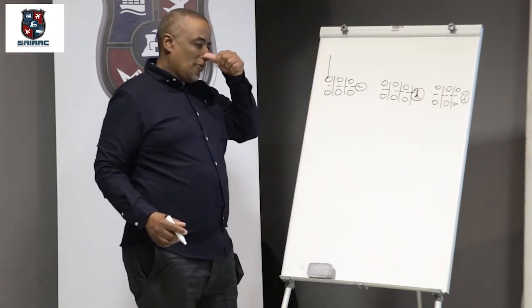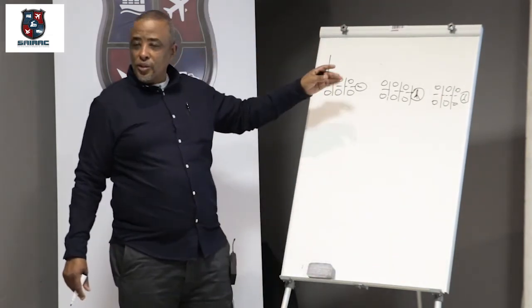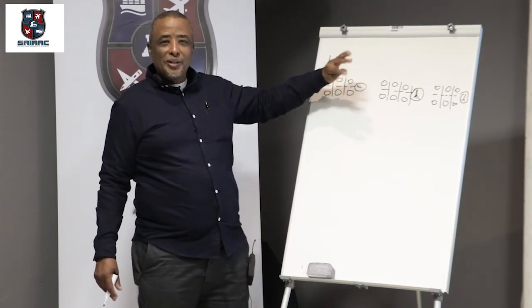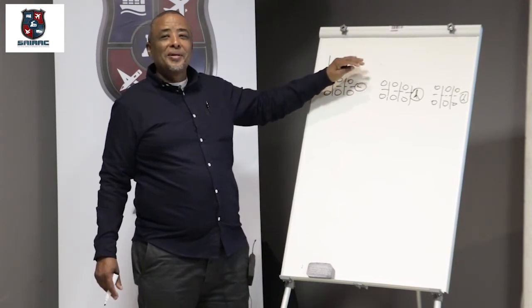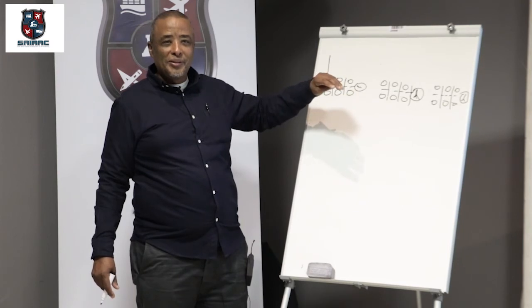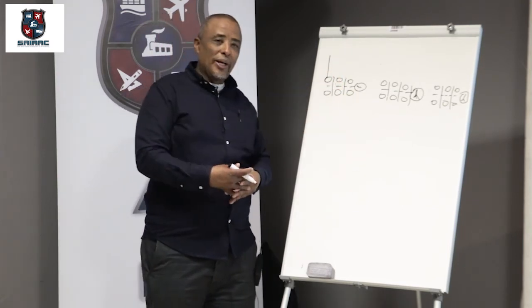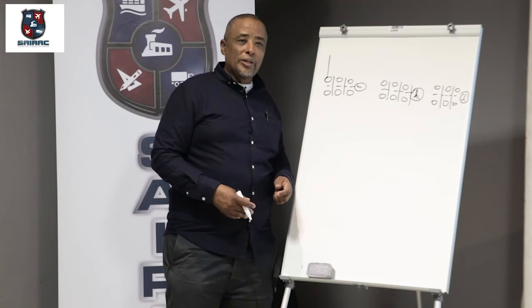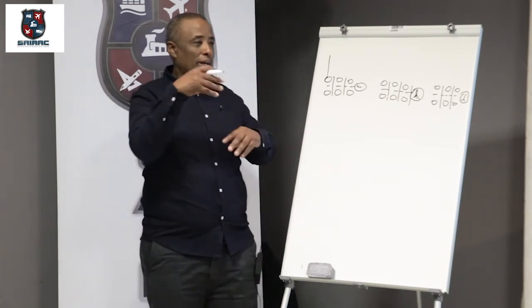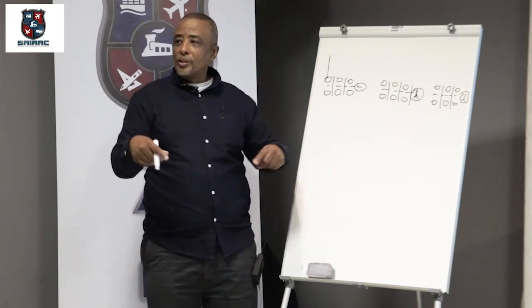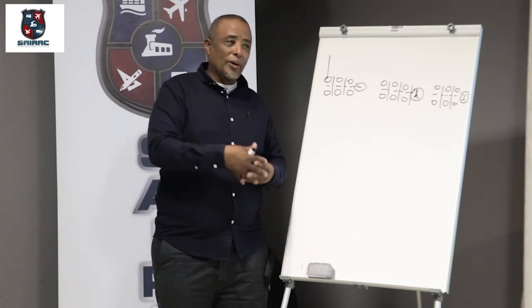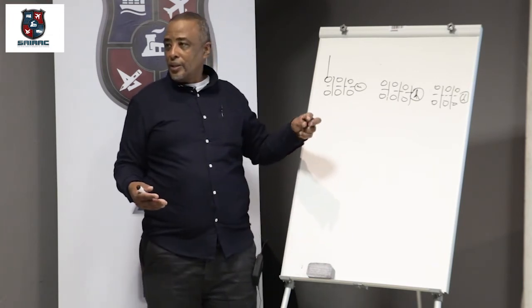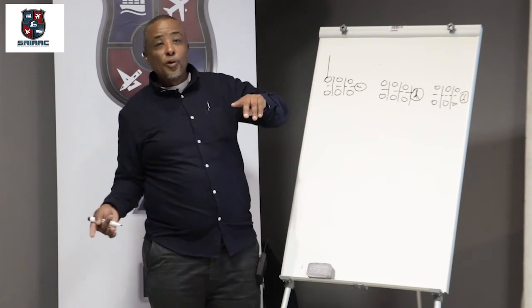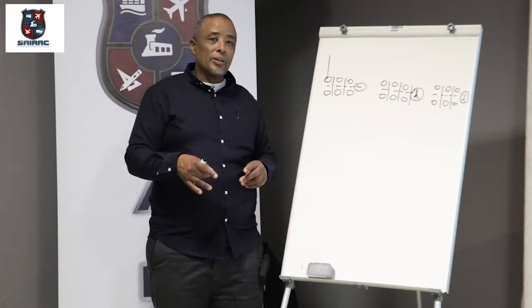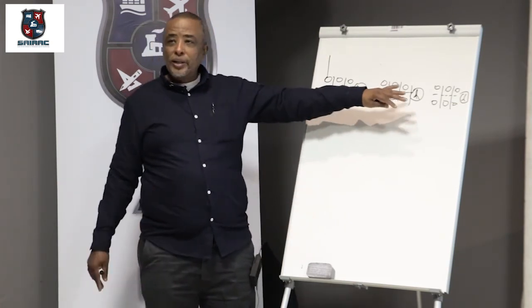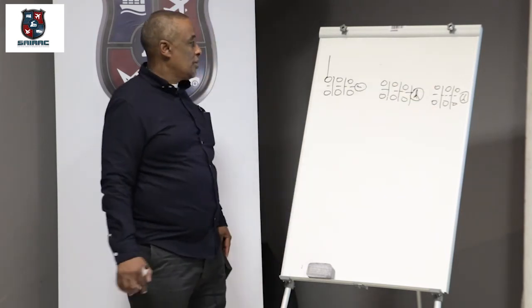Okay, there's something that I forgot to mention. Forward and reverse contactors, what did I leave out there? The overloads were there, the interlocking. Okay, sometimes it's mechanical, but you must also do electrical interlocking. Sometimes it's mechanically, you try to push one, the other can't. But over and above that, you need to have the electrical interlocking. So when it's in forward, it can't go in reverse. Okay, same thing here, we need the interlocking here for main, star, and delta.